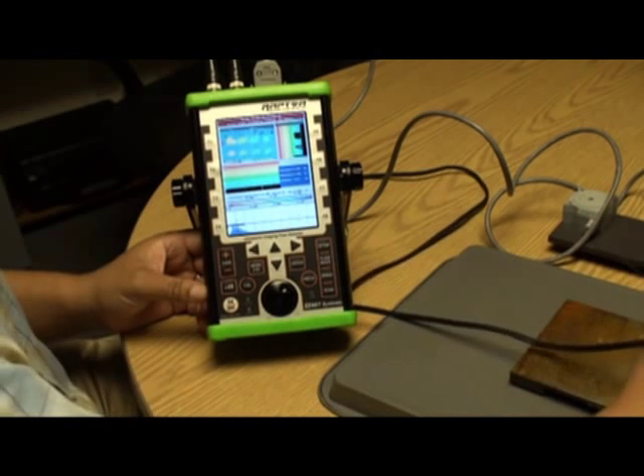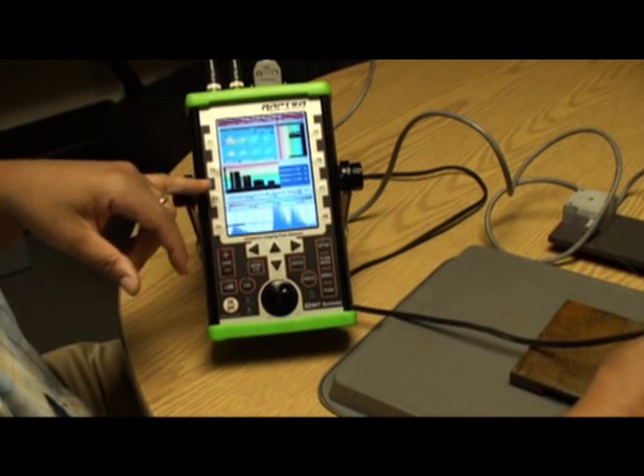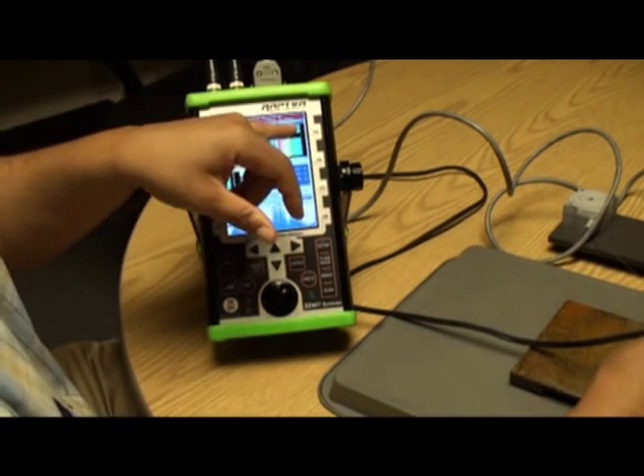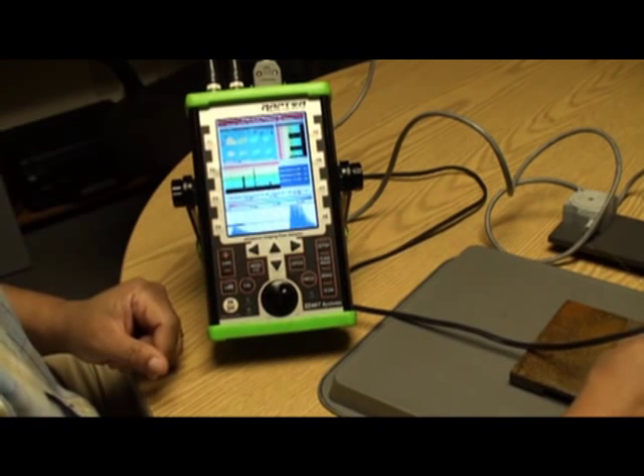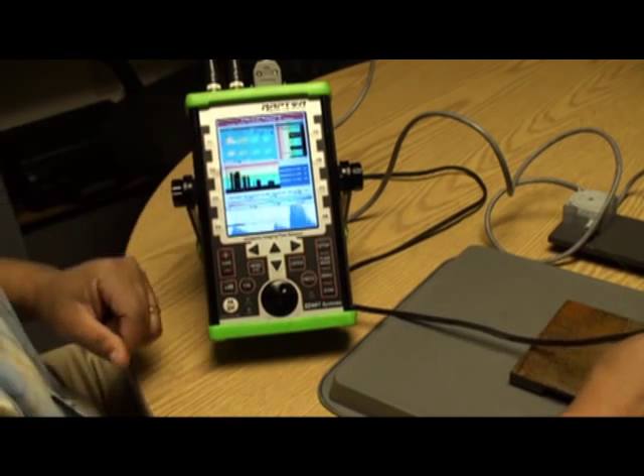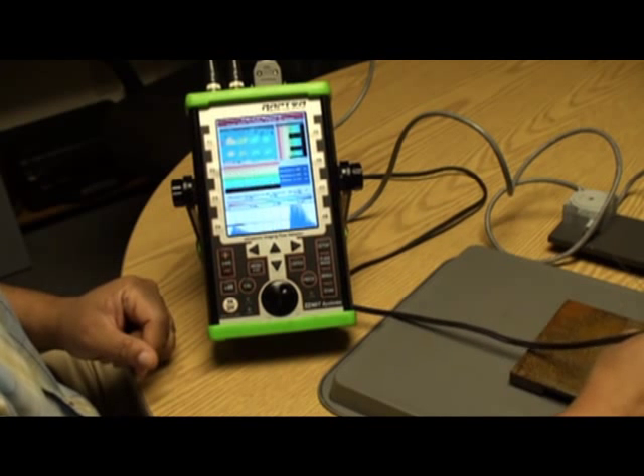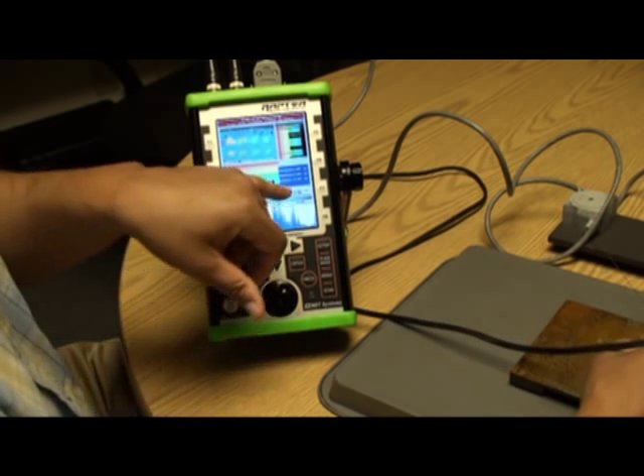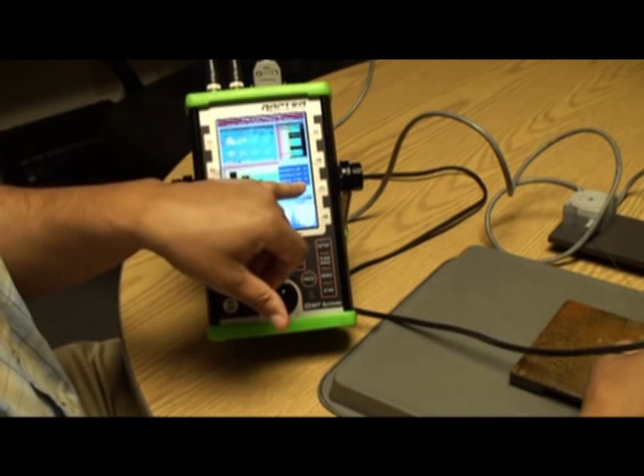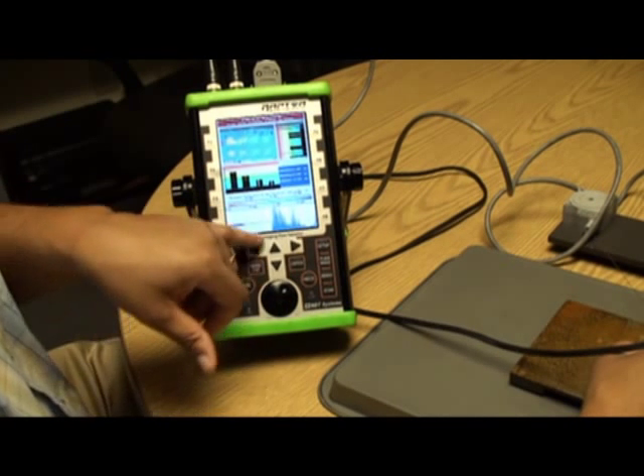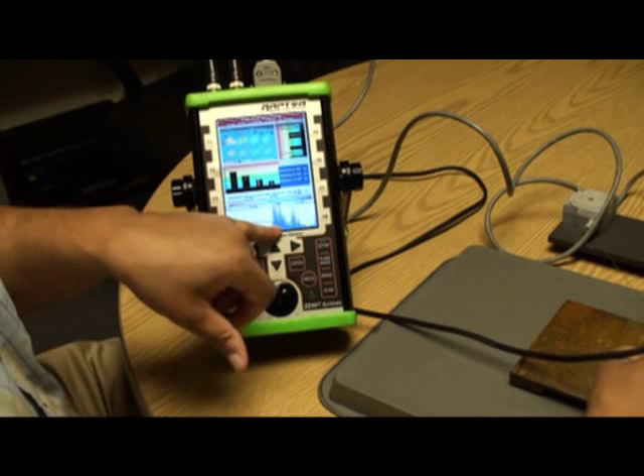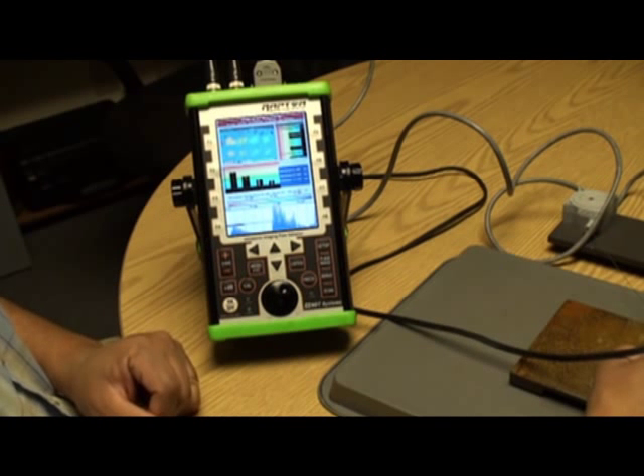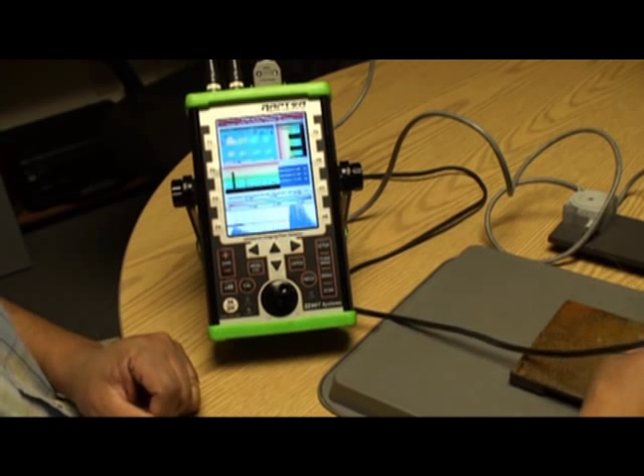Our B-scan basically, we have a B-scan that shows a cross-section in two directions by looking at the crosshairs and wherever the crosshairs move, the center of the crosshair will give you the value of the depth of the corrosion and we also allow you to see the A-scan live waveform of the defects that we're seeing.